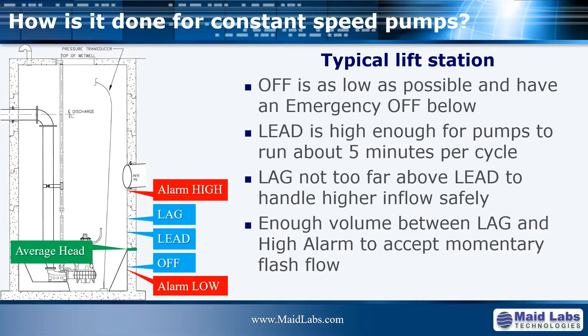When you calculate the actual pump capacity, when you do a drawdown calculation, you do it for an average head, which is usually between the lead level and the off level. That's how you calculate it, and it's for that level that you calculate flow rate. So when you calculate a pump capacity of, let's say, 500 GPM, you know that it is for the head that is right there between the lead and off level, if you have used, of course, these levels to calculate it. Now that we know how a regular lift station works, and by the way, one of the reasons why it works this way is because you want to have as much volumetric capacity above the lead level to be able to accumulate water in case you have a peak of flow rate coming in, and to be able to accumulate that water before it goes through an overflow pipe if you have one, or goes back to the suppliers of that water.